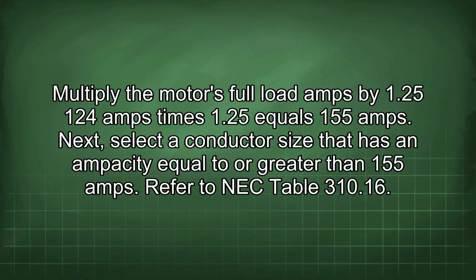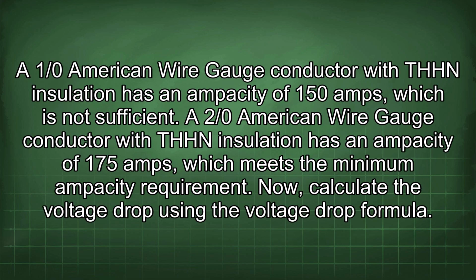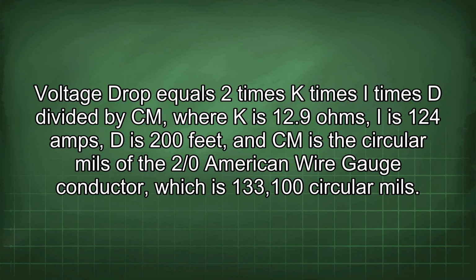Next, select a conductor size that has an ampacity equal to or greater than 155 amps. Refer to NEC Table 310.16. A 1/0 American wire gauge conductor with THHN insulation has an ampacity of 150 amps, which is not sufficient. A 2/0 American wire gauge conductor with THHN insulation has an ampacity of 175 amps, which meets the minimum ampacity requirement. Now calculate the voltage drop using the voltage drop formula.